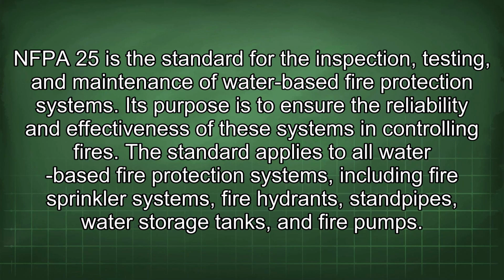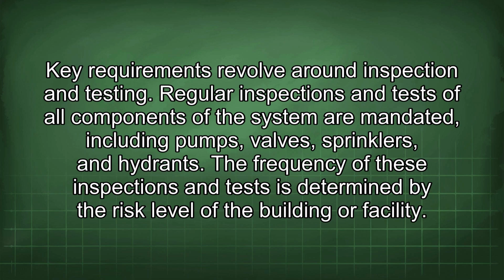NFPA 25 is the standard for the inspection, testing, and maintenance of water-based fire protection systems. Its purpose is to ensure the reliability and effectiveness of these systems in controlling fires. The standard applies to all water-based fire protection systems, including fire sprinkler systems, fire hydrants, standpipes, water storage tanks, and fire pumps. Key requirements revolve around inspection and testing.